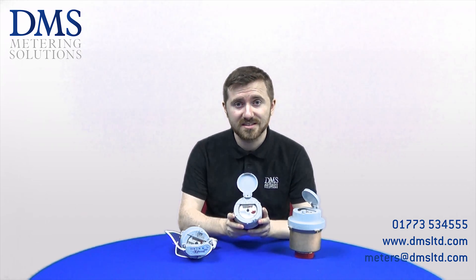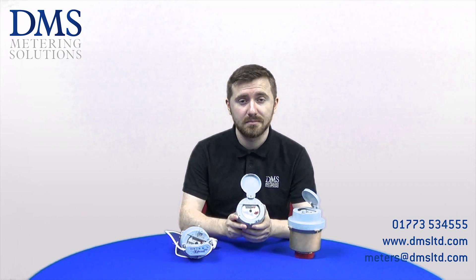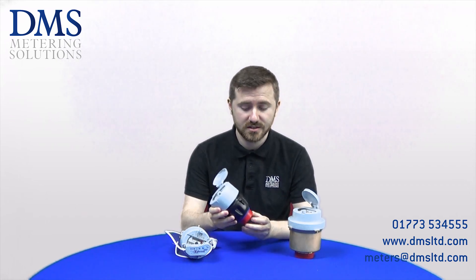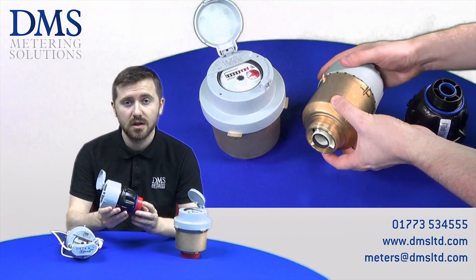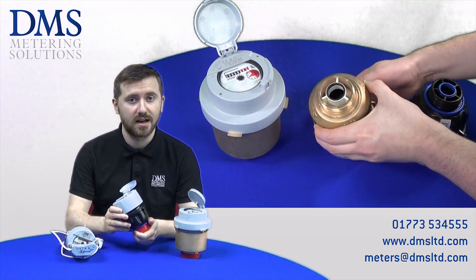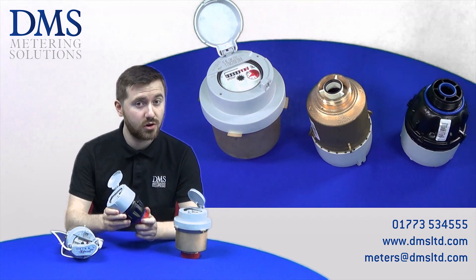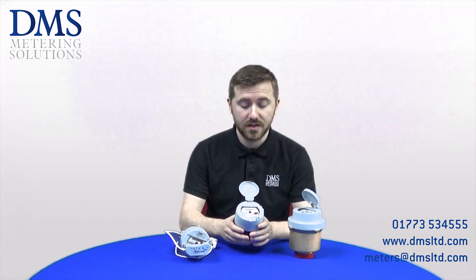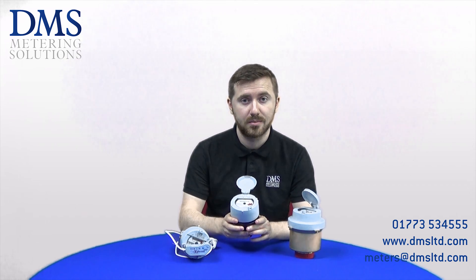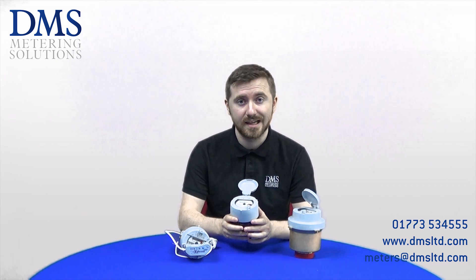The V210 range are a concentric style of cold water meter manufactured by Elster, who are now a part of Honeywell. What we mean by concentric is that the meter design has just a single thread on the bottom, which allows them to be installed in manifolds, meter carriers, or boundary box installations that you would find perhaps outside your home. These meters are WRAS and MID approved, which allows them to be used on potable installations across the UK and also for billing purposes. Their maximum operating temperature is 30 degrees C, so they are rated only for cold water applications with 100% clean mediums.